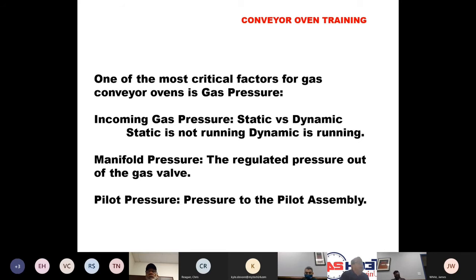The second pressure we're always checking is manifold pressure. Manifold pressure is the pressure that we're going to regulate out of our gas valve, and this is the pressure that our burner is actually going to operate on. It is usually about 3.5 inches of water column, but you always want to verify that with your data plate. There are some ovens out there that will run at 4 inches of water column.